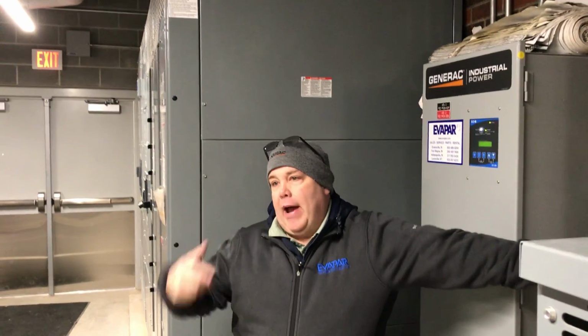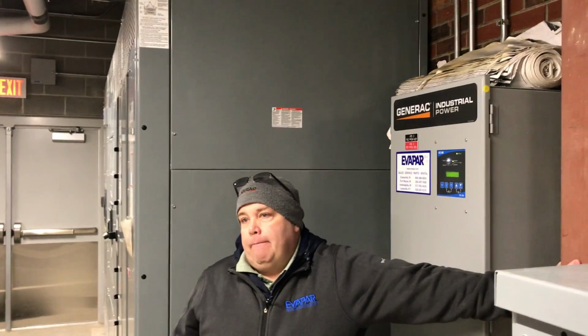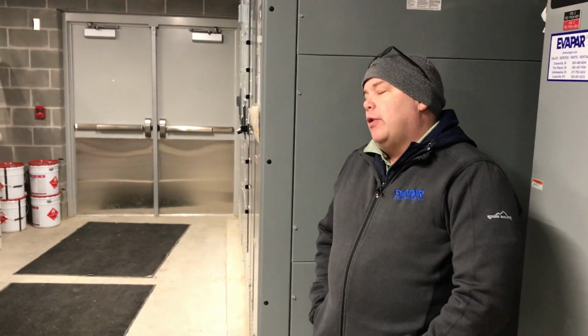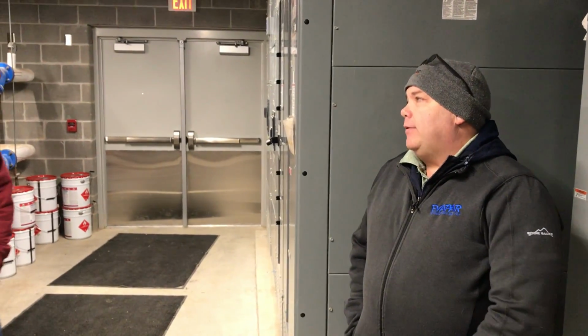It's just not seeing 120 volts from here to charge it through the battery charger. So you're saying when it runs and everything normals up, you've got an alarm, or just when it's running? No, it's the generator that's in alarm. We're gonna have that on Monday, a test, right? It would just be in the situation if it transfers, if we lose power. If you lose power, you'll see that.